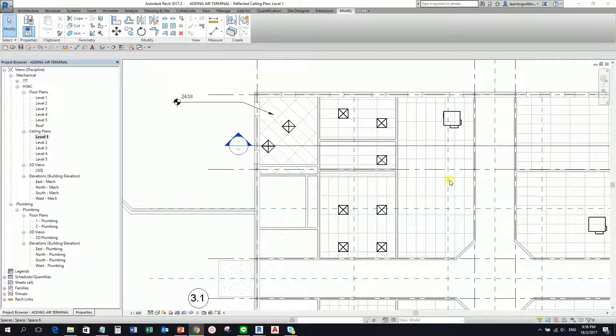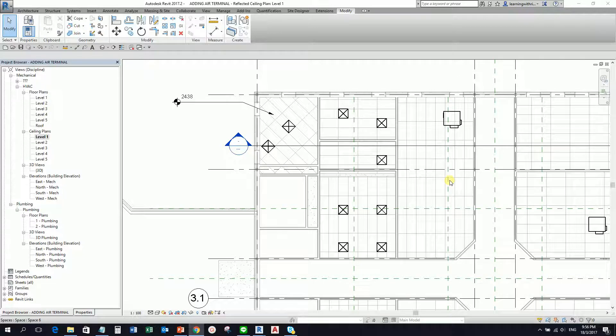I prefer the air terminal as a non-hosted family. Why? Because if the architect changes the height of the ceiling and your air terminals are ceiling-hosted, the air terminals will also move with the ceiling. When that happens, the connections from the air terminals to the duct will get lost — all the connections will break. That's why most of the time air terminals should be non-hosted; I prefer them floating rather than risk breaking the duct connections.